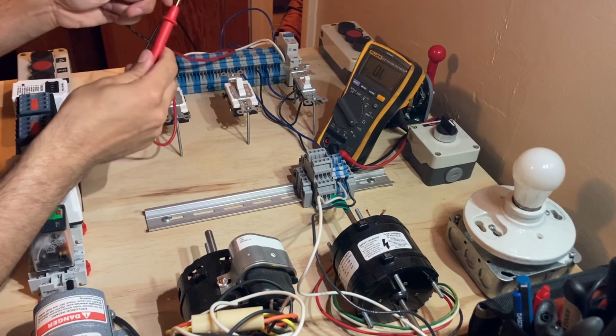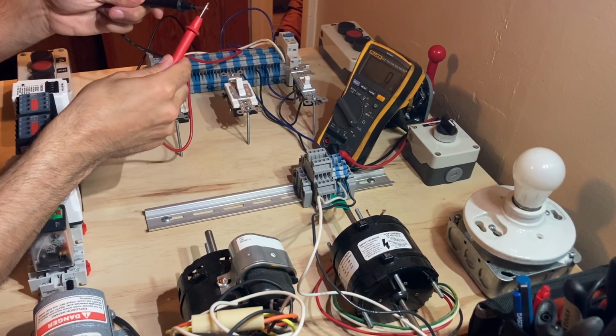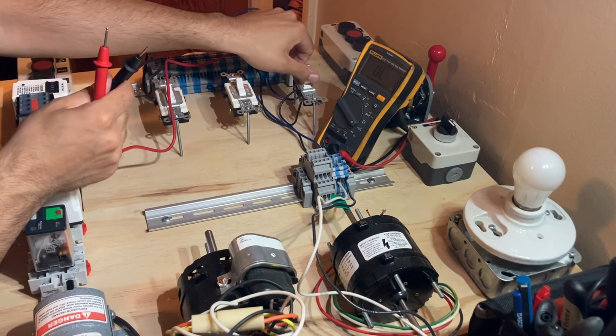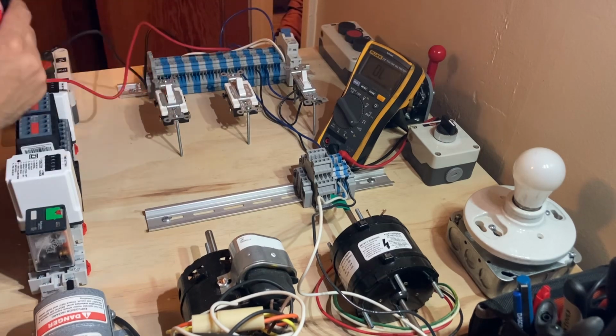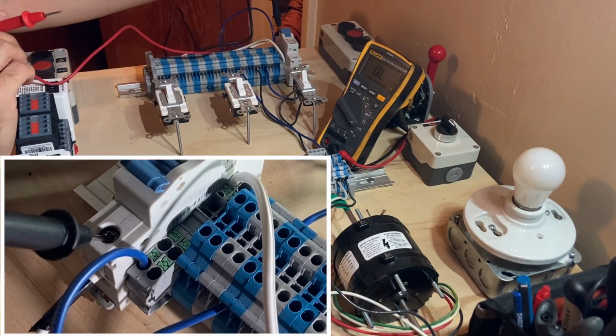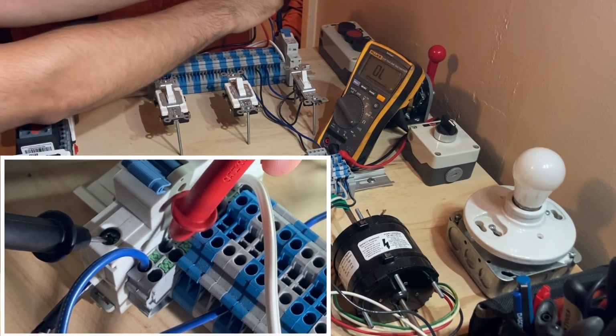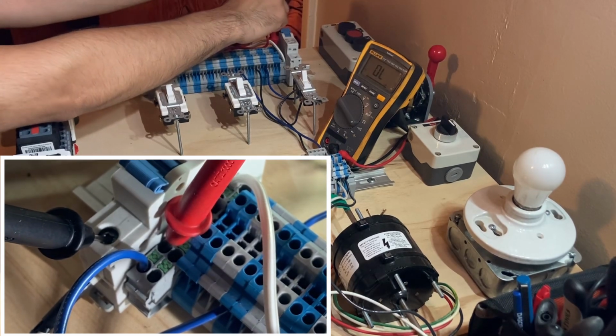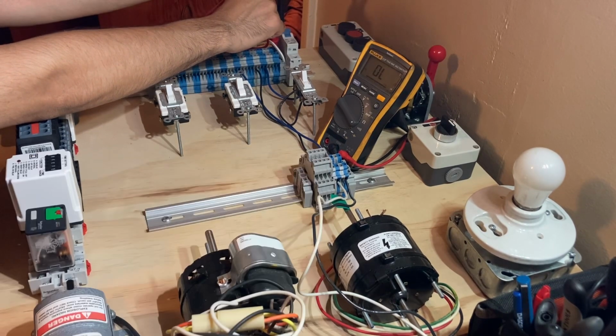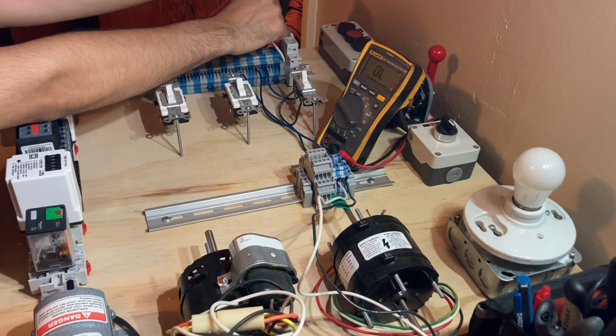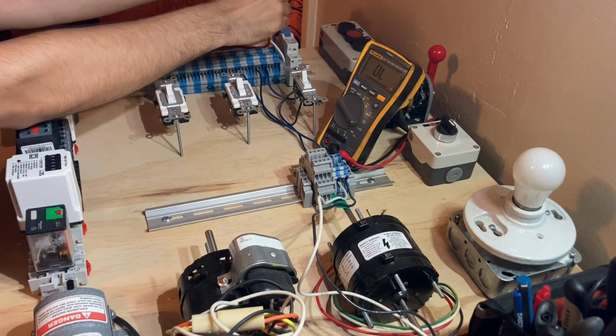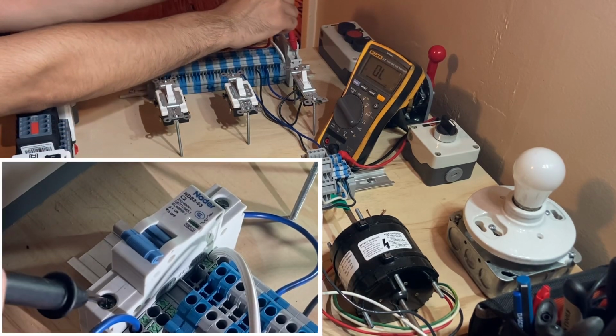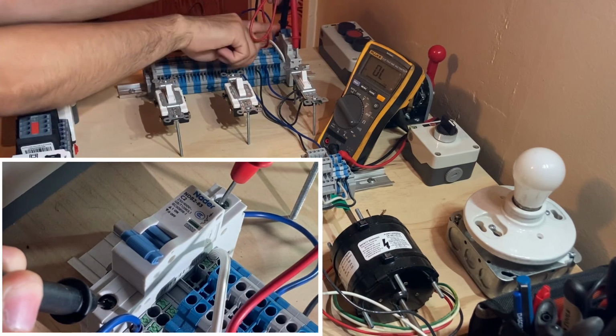It's important to know how to trace our circuit with continuity and with voltage if you want to become a good troubleshooter. So here we start by checking our line side and our neutral on continuity, and we read OL. This is good because we don't want a connection between those two. That would be a short circuit.